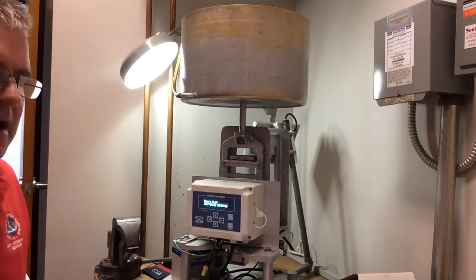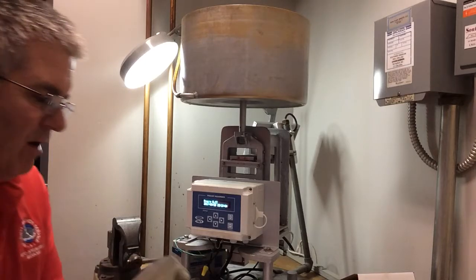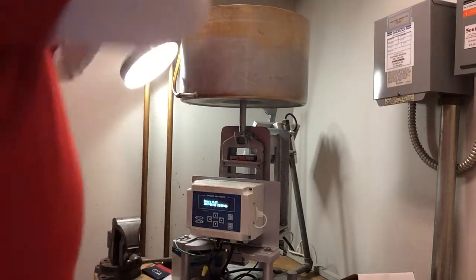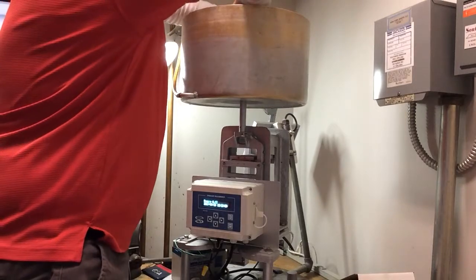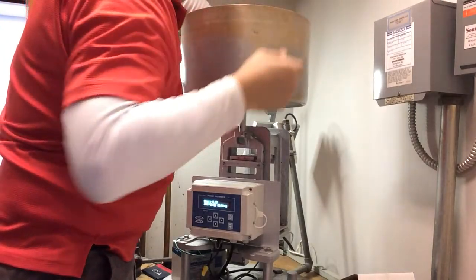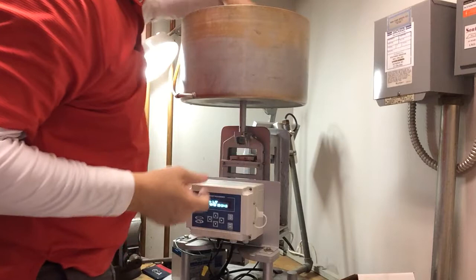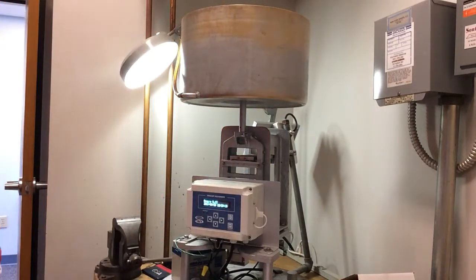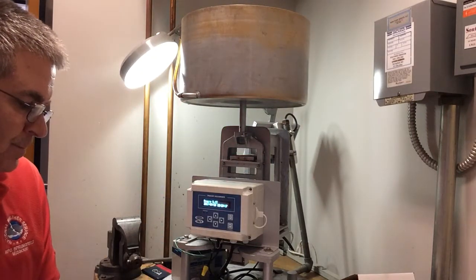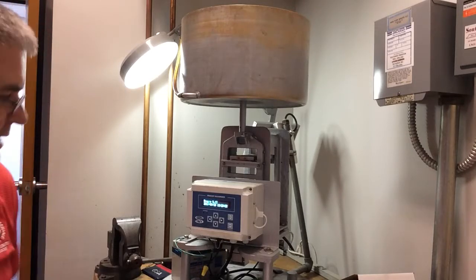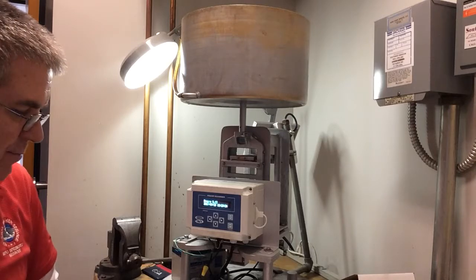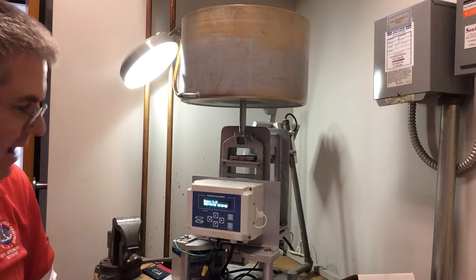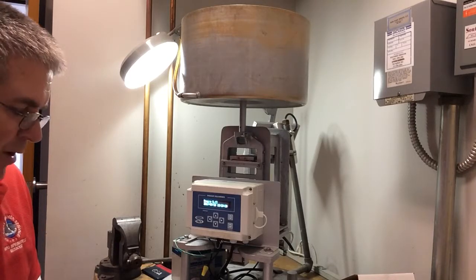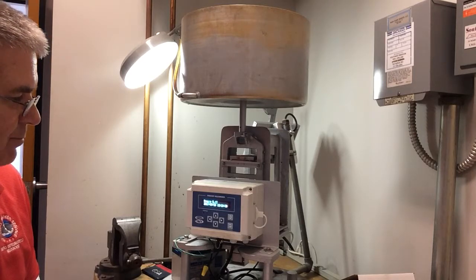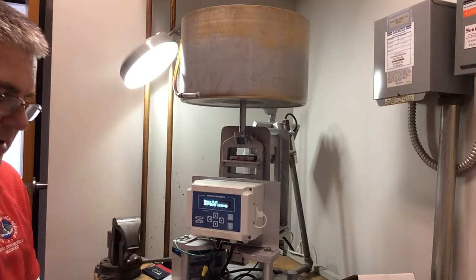Once that's written down, you can take a 4,100 gram size weight, and we're going to set it gently into the bucket. We're going to let that stabilize a little bit. We're going to write that value down, and subtract the 0.13 that we had as empty. This one's showing 5.13, subtracting 0.13, so we get a reading of 5 inches.